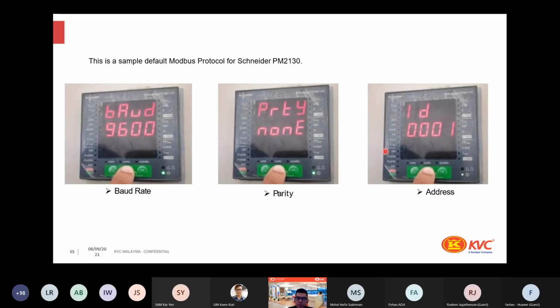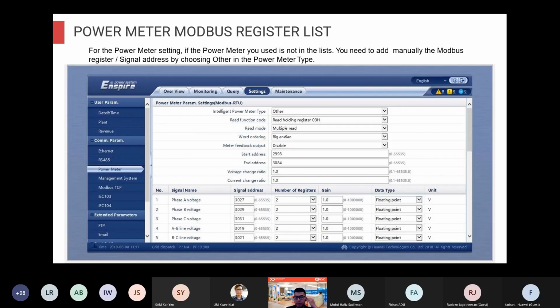So please always ensure it's the same address. Next, the power meter Modbus register list. Recall why other brands of power meters can also connect to the Smart Logger - the DPM list in the manual and my slides just means it's pre-configured. If you want to use a different brand, go ahead, because you can manually insert the Modbus register list.